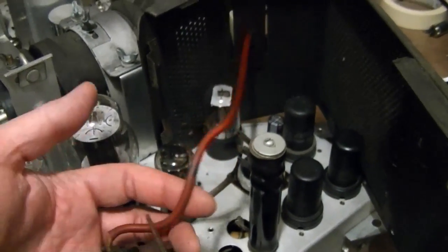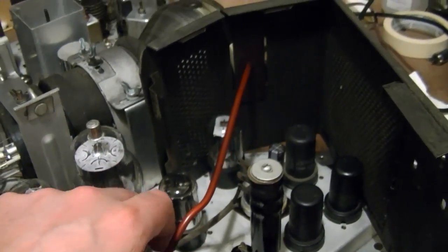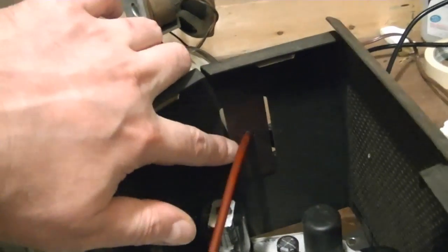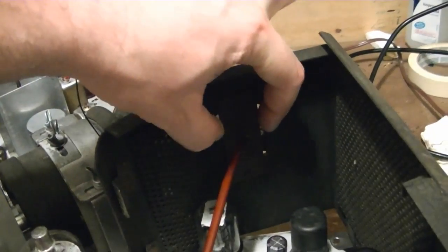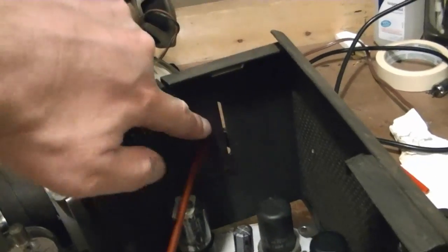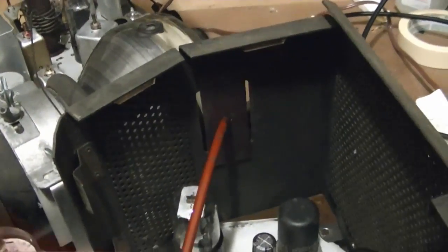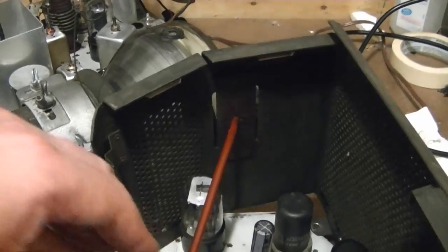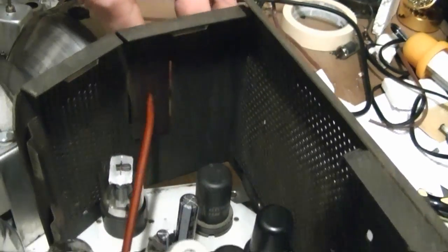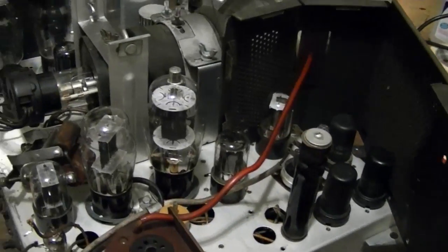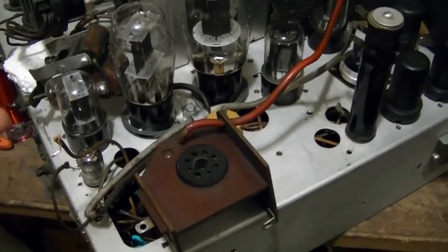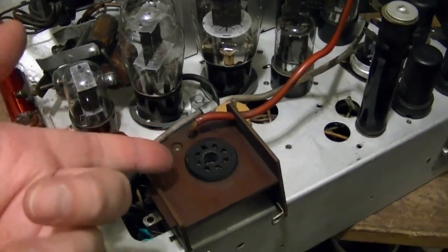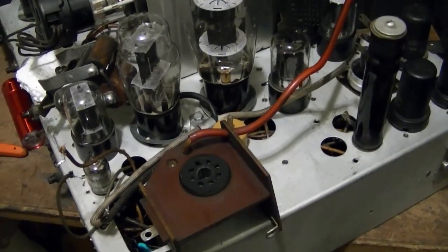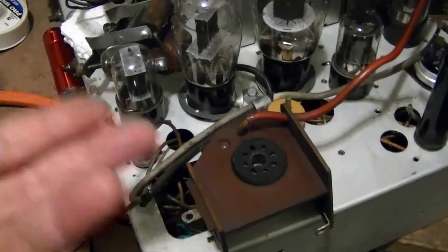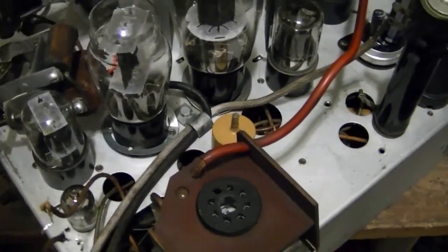Or, if this high voltage lead was brushing up against something, they've got it going through a similar piece of material here, so there's a pretty big gap around all sides, but could be a carbon track burned through here, I suppose, although the insulation seems to be unbroken, and I've positioned this at different points through that hole, so I don't think there's any issue there. And really, if there was some arcing or leakage through here, I'd probably smell the corona, or hear the sound, or there'd be some obvious charring. There'd be some evidence of the issue.